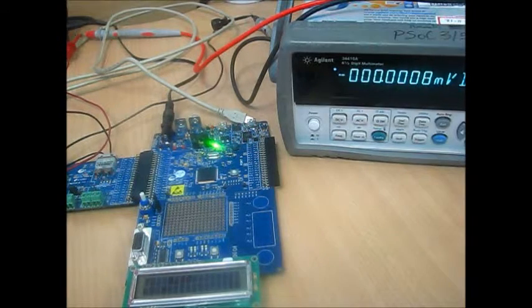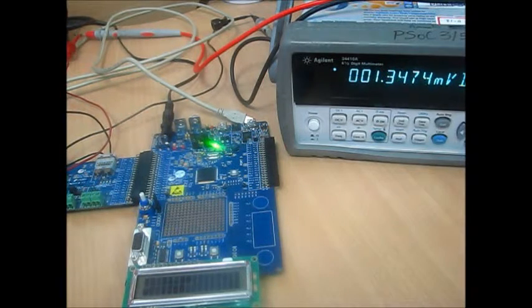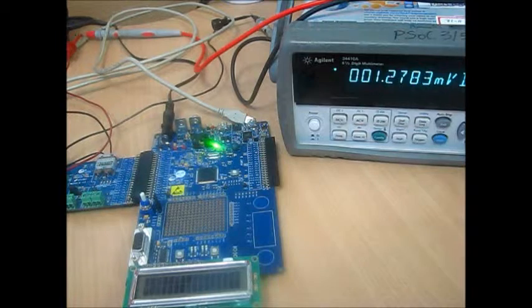Let's change it to a little higher value. I change it to somewhere close to room temperature, which is around 1 millivolts. Now, as you see, the multimeter reads 1.25. It varies a little because it takes some time for the potentiometer to settle down. From the look, you can say that both the LCD and the multimeter are very close. They have a difference of around the maximum of 6 to 7 microvolts, which is at the maximum point 2 degrees Celsius.